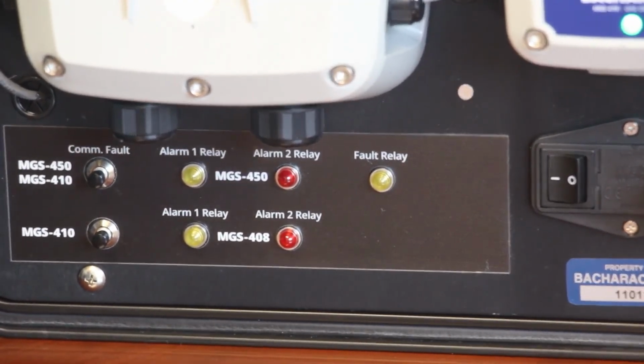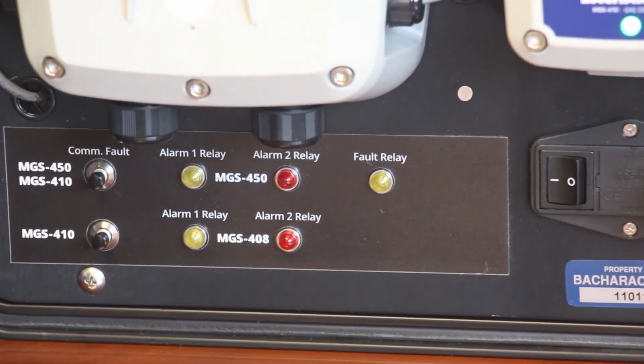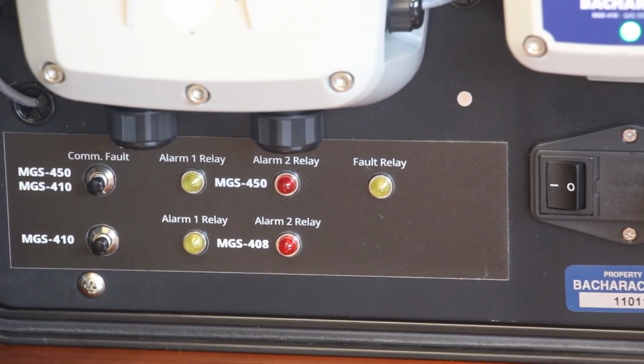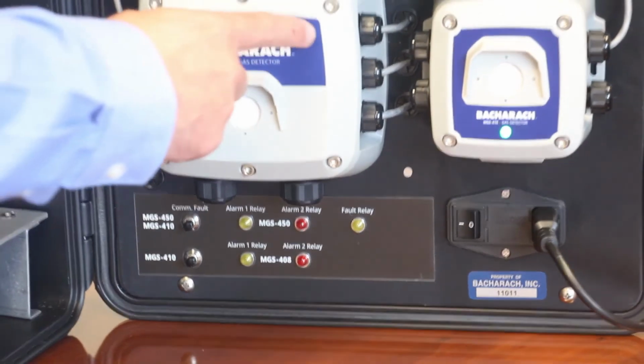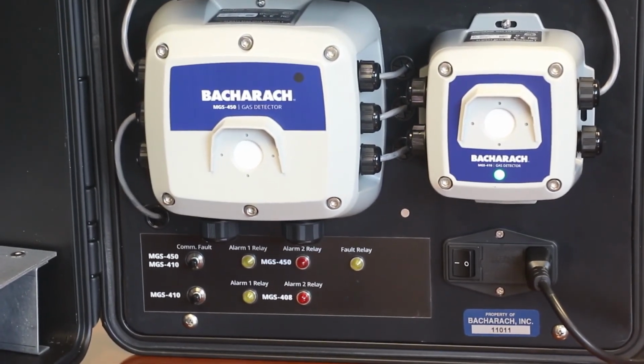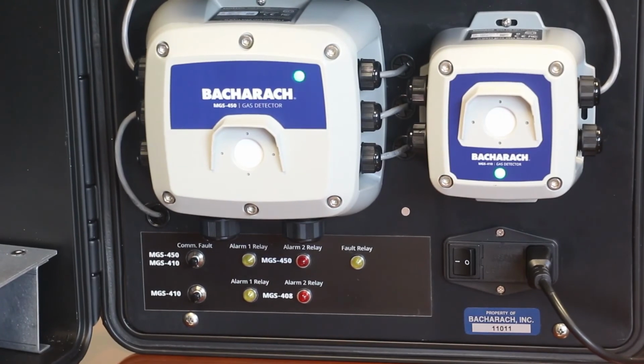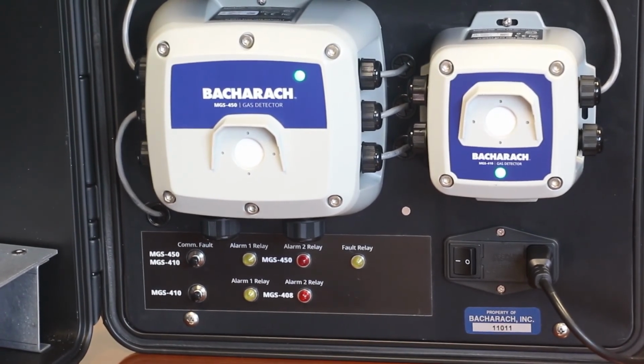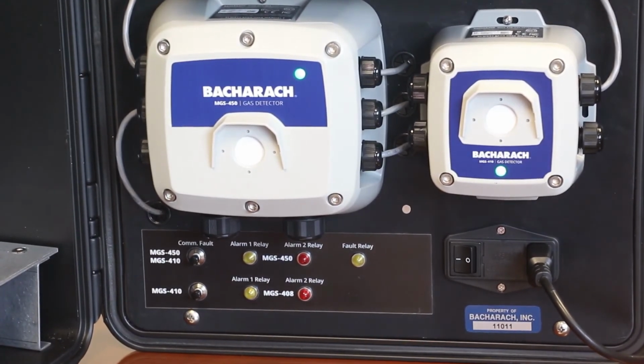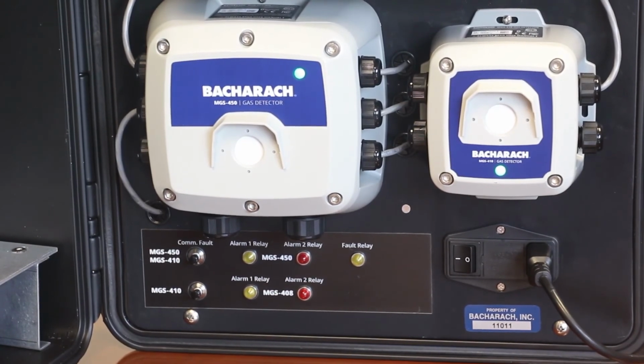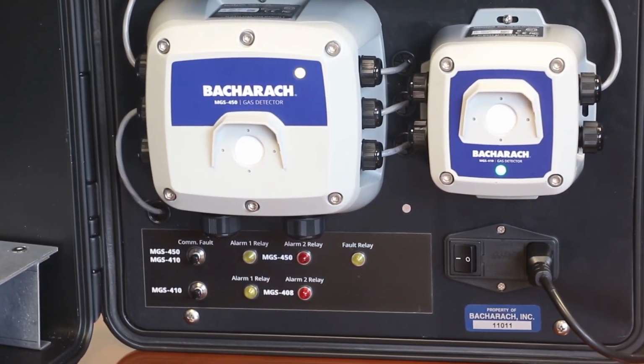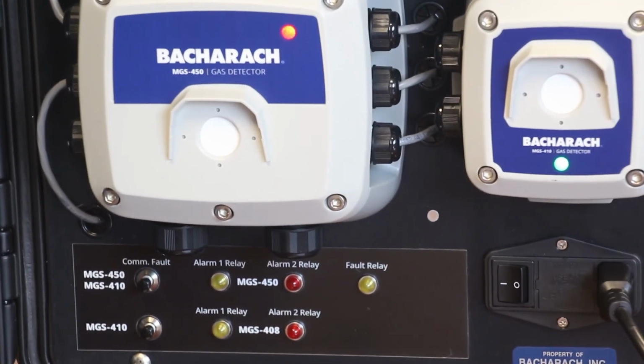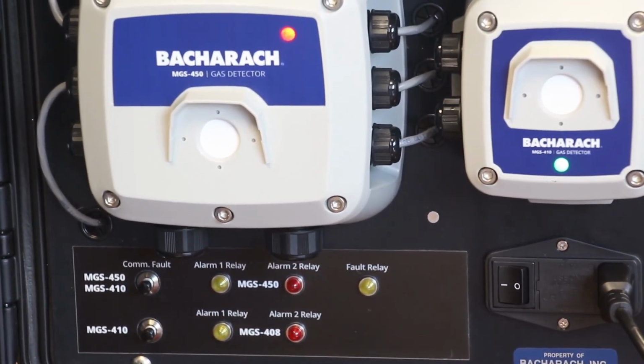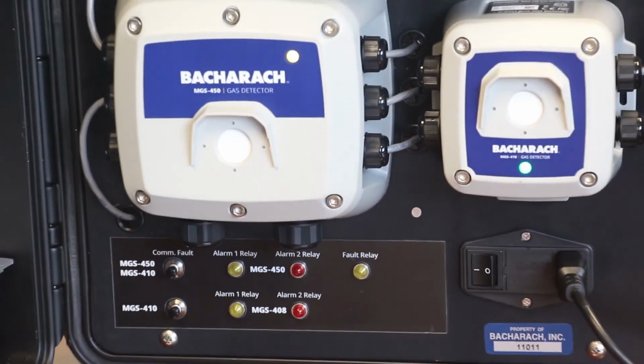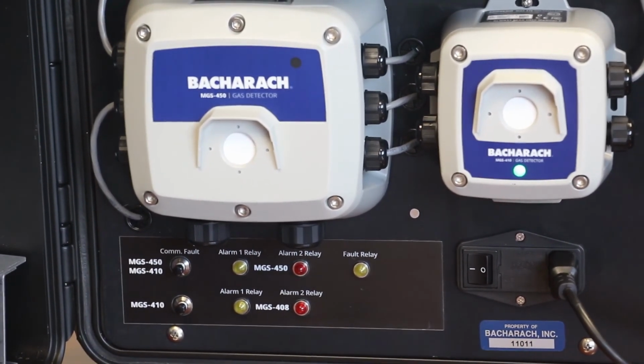Okay, so we're still in output test enable mode for the MGS-450, which is this detector here on the left-hand side. You'll see at the moment that the LED is switched to off. You have that off in the app here. If we cycle through, we have green, which is usually the standard operating LED color that you would see to indicate that the system is healthy and operating correctly. We have orange, which is usually a first stage alarm. And then we have red, which is a second stage alarm or a fault on the system. So again, you can quickly cycle through those. We have the internal buzzer.